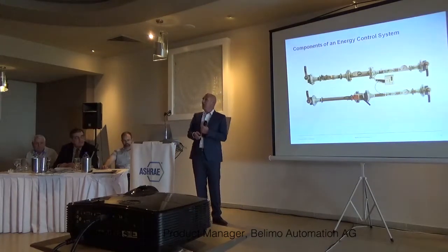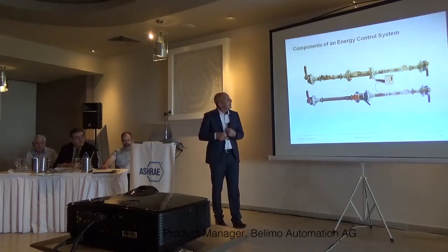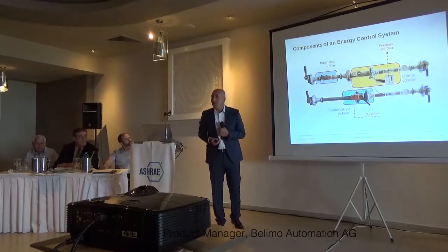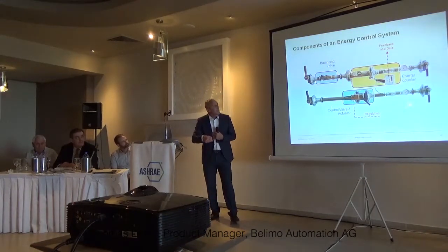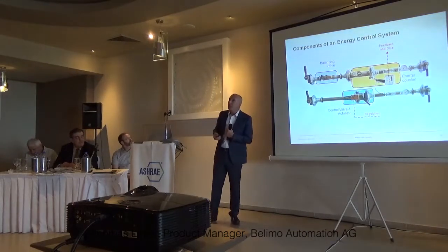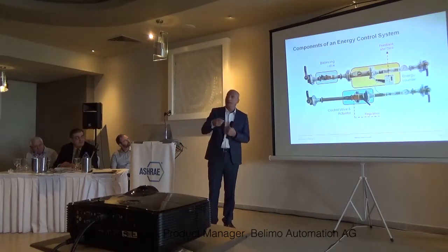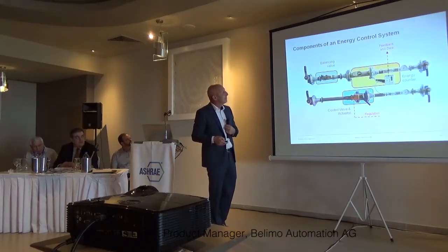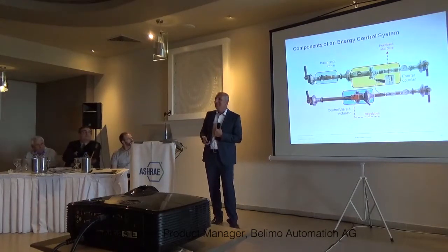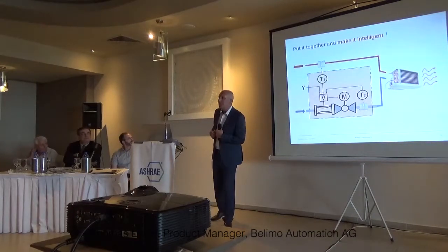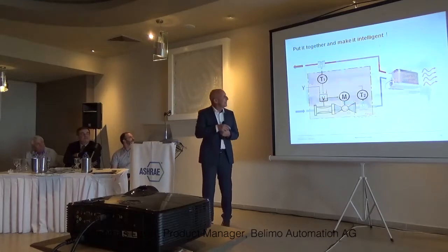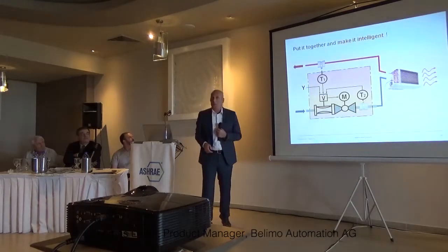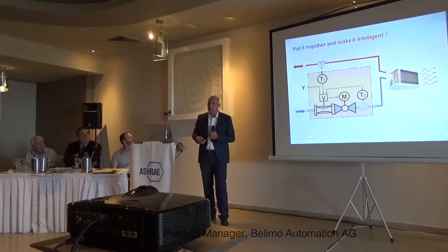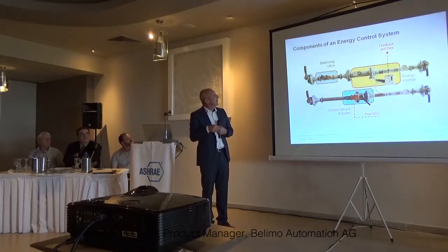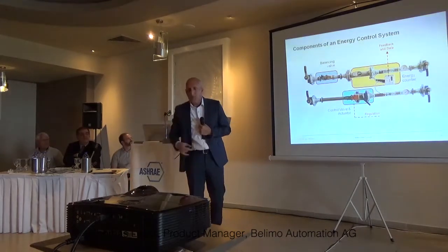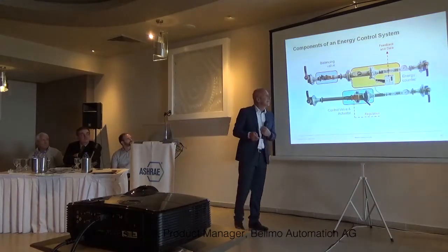Well, we started with a quite simple thing. What's the industry standard currently? Industry standard will be to use this setup: a control valve with an actuator, energy counter, balancing valve. That was the start. And then we found this is not enough because you have to put some more things inside. It is a good thing to start with, this concept, but what was very much missing is intelligence. With the normal setup here, you have components normally from different suppliers. You have to select, you have to pick together, you have to look if the thing is matching well together.